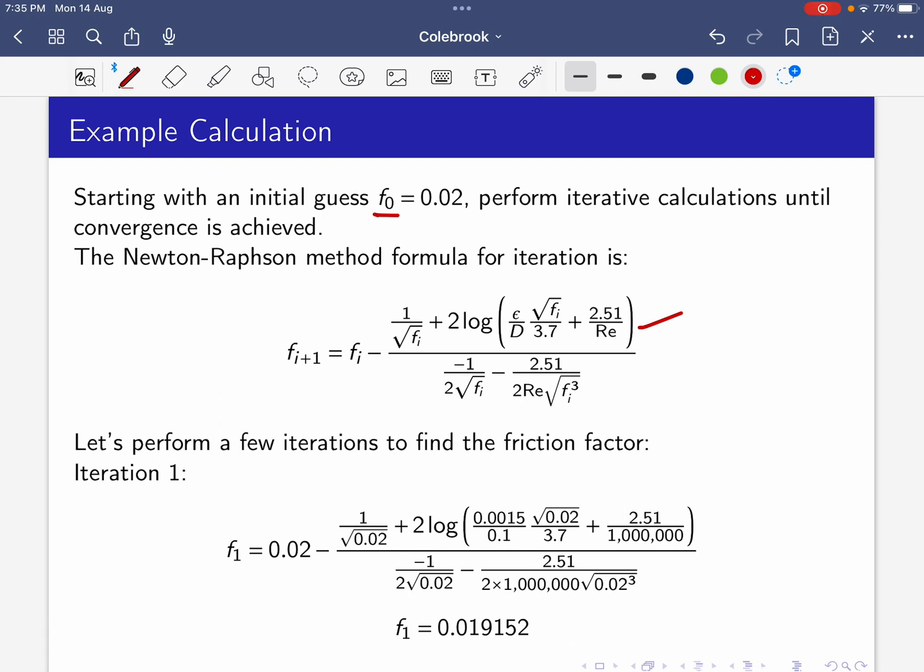Performing iteration one: f₁ = f₀ minus the ratio. f₀ is 0.02. Plugging in all values with the already calculated Reynolds number, epsilon value, and diameter, we get f₁ = 0.019152.